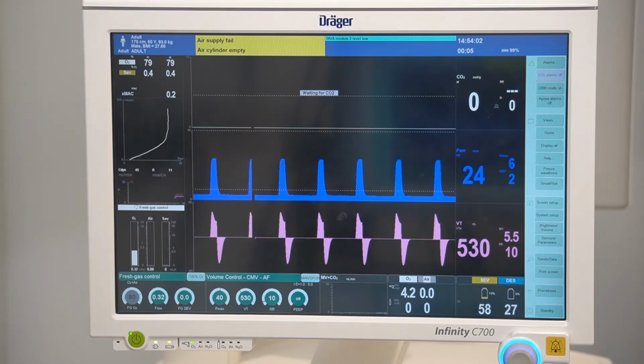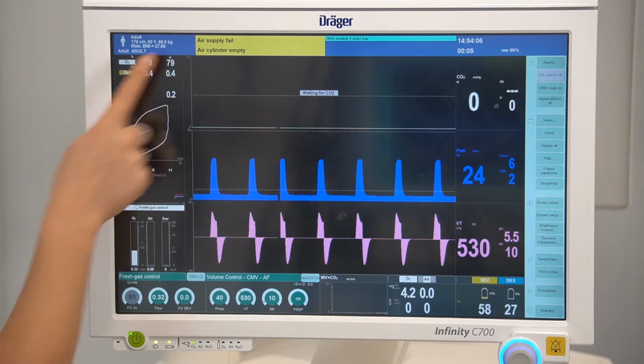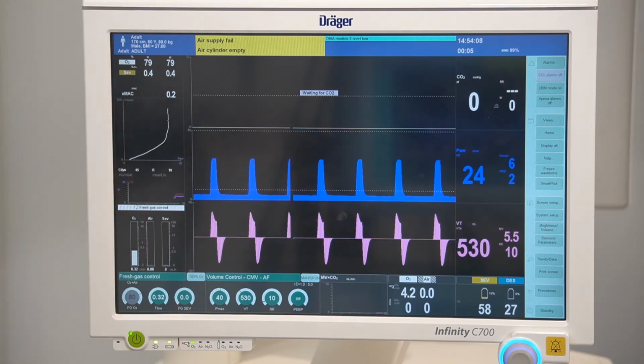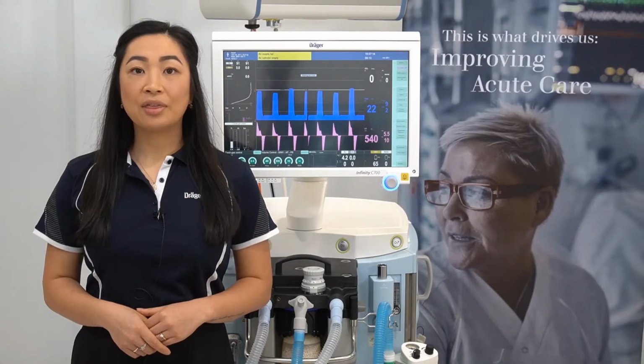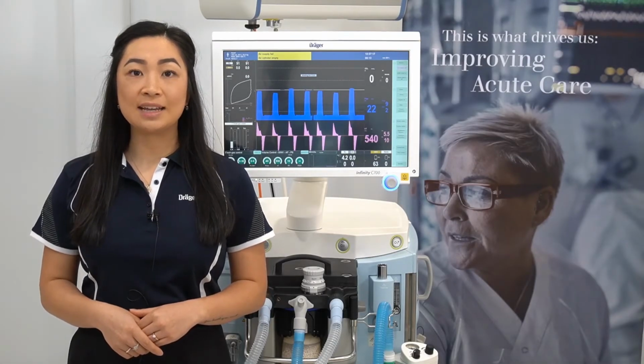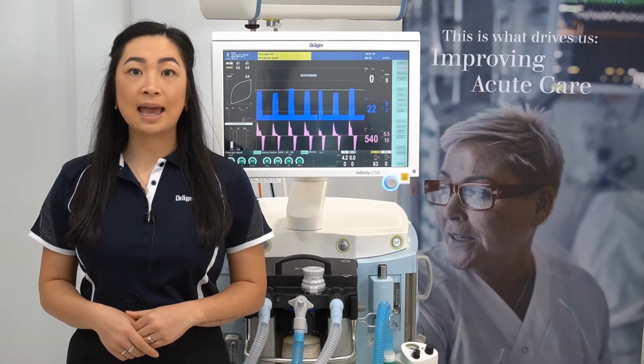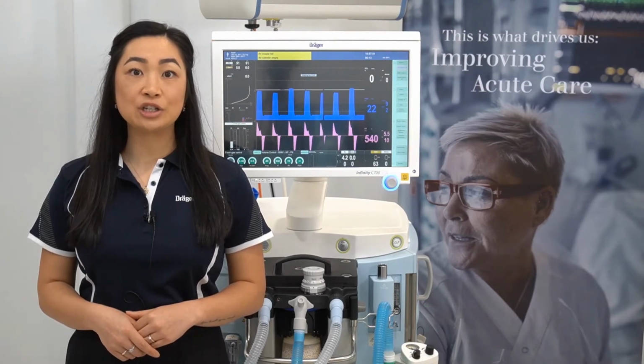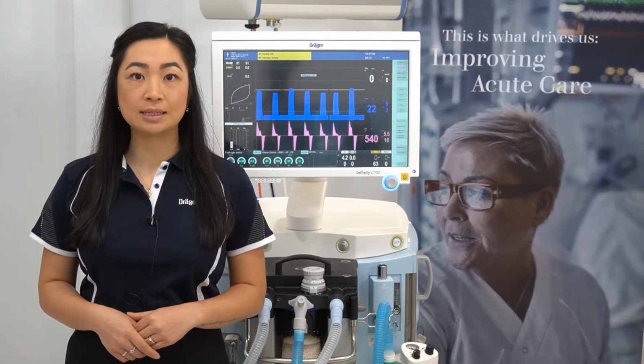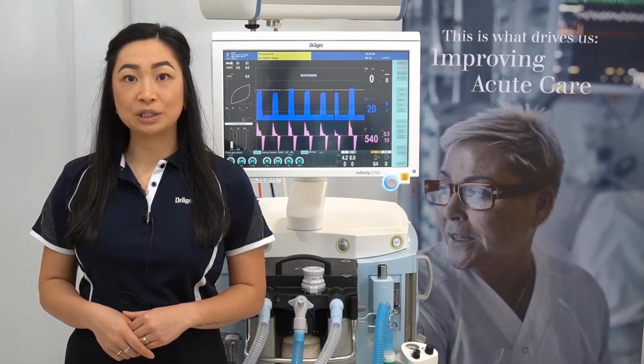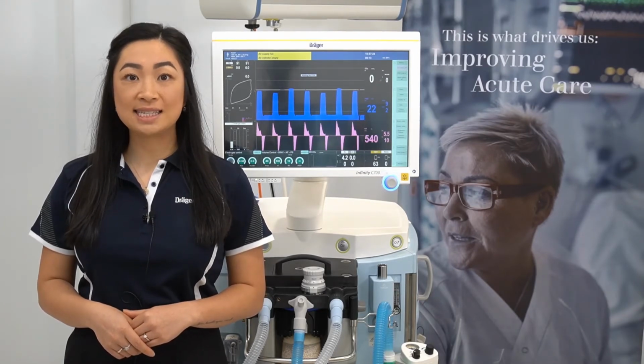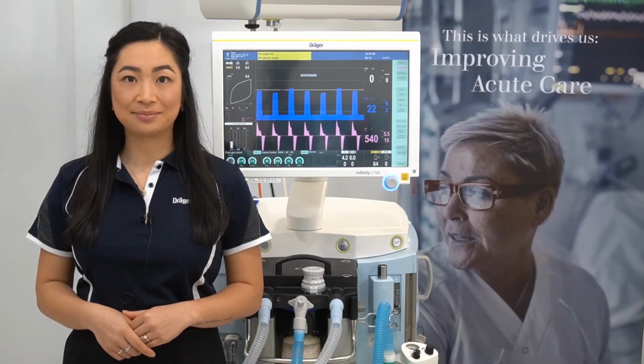DIVA metering modules require air as a driving gas. So if air becomes unavailable, you will not be able to utilise the DIVA metering modules. There will be an air buffer in the DIVA metering modules to allow volatile agent delivery to continue for a couple of minutes, while the user re-establishes air supply or transitions to intravenous drugs.